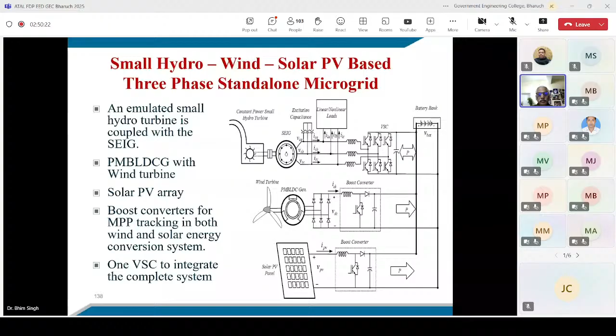Of course, with the support of the battery, you can take power from the battery and you can feed power to the battery. But the variable wind speed as well as the variable generation from solar comes to the DC-link, which charges the battery if there is surplus power. Otherwise, it feeds the load. So the intermittency of the load, the wind generation and the solar generation is taken care of by the battery only. And we are using only one voltage source converter.